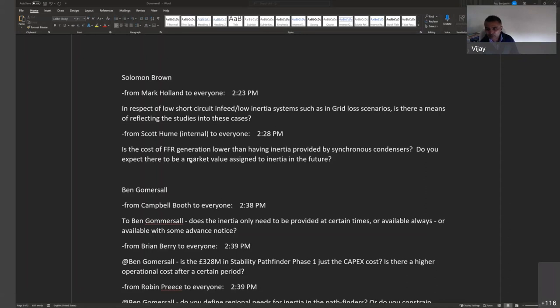There's a couple of other questions. I can see one from Seamus, which is for you, Vijay. Could you elaborate on why a transformer impedance should be different for a synchronous condenser than it is for a normal generator? Yeah, if you look at it in a very non-technical way, the machine, for a fault, is going to inject a lot of short circuit current. It means your winding is going to be thicker. You have a large machine sitting there which is going to be feeding the fault. It means the impedance of the transformer should justify injection of that current, and that's why when you design the whole system, you will see the impedance of the transformer is low.